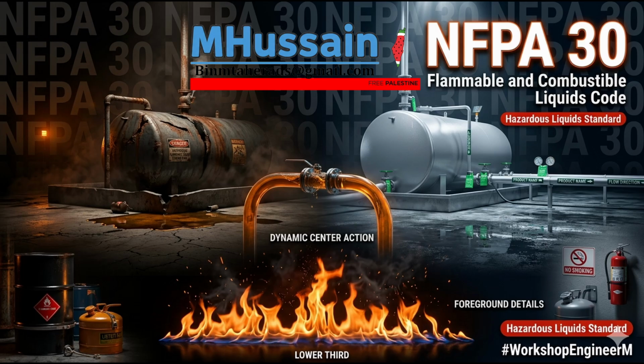Never, under any circumstance, assume the hazard classification of a liquid based on its generic commercial name. This is a subtle trap that frequently catches junior planners, isn't it? Constantly. An operator might say, oh, we're just storing standard cleaning solvent, or it's just a light adhesive. You cannot design a life safety system based on a colloquial label. Ignitable liquid is a massive umbrella.